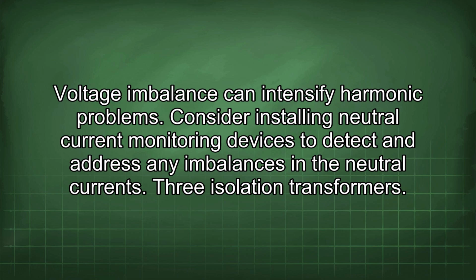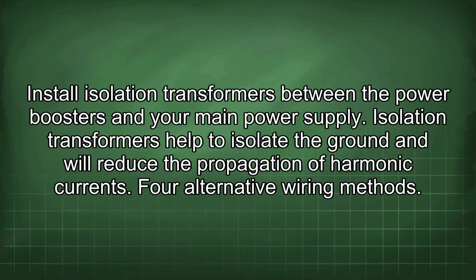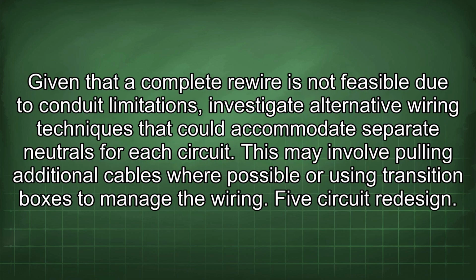3. Isolation transformers. Install isolation transformers between the power boosters and your main power supply. Isolation transformers help to isolate the ground and will reduce the propagation of harmonic currents. 4. Alternative wiring methods. Given that a complete rewire is not feasible due to conduit limitations, investigate alternative wiring techniques that could accommodate separate neutrals for each circuit. This may involve pulling additional cables where possible or using transition boxes to manage the wiring.